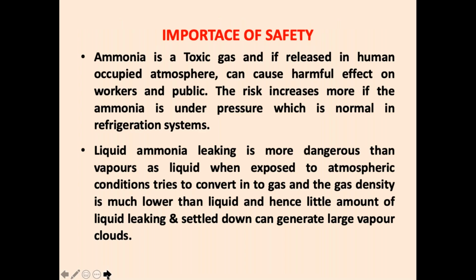Because ammonia is a toxic gas, and if released to the atmosphere in an occupied area it can cause harmful effects to workers and the public. The risk increases especially when ammonia is under pressure, and in our refrigeration systems, normally ammonia is under pressure. Now, the next point is very, very important. Most people don't realize it. Liquid ammonia leaking is more dangerous than vapor.